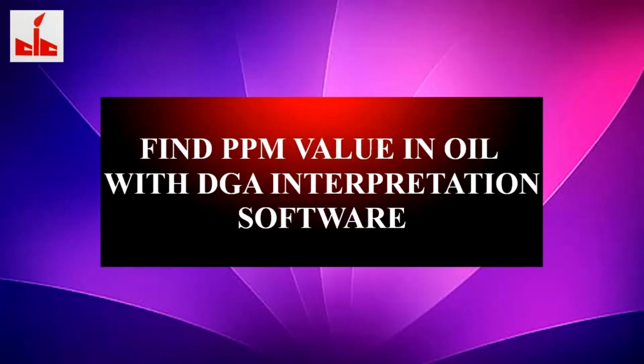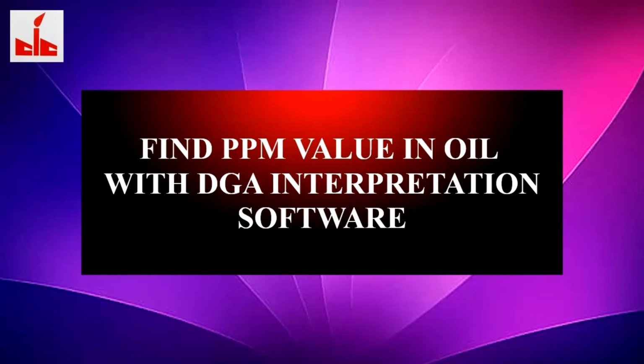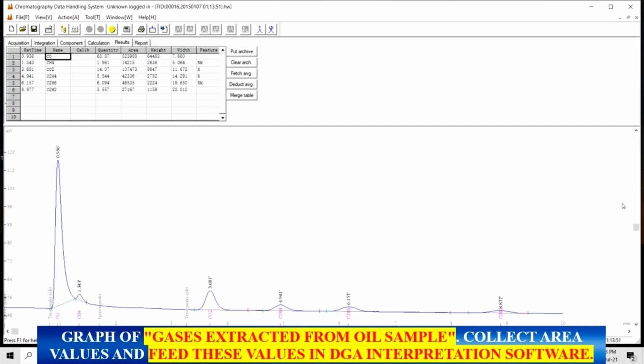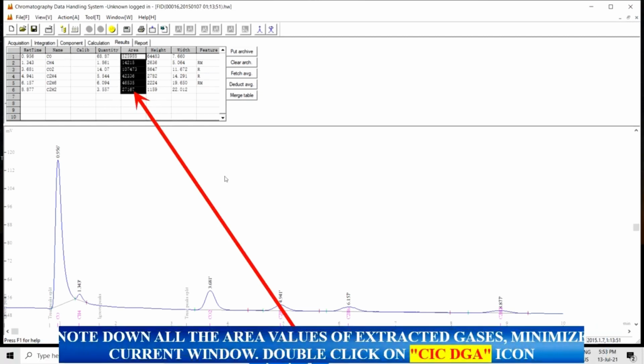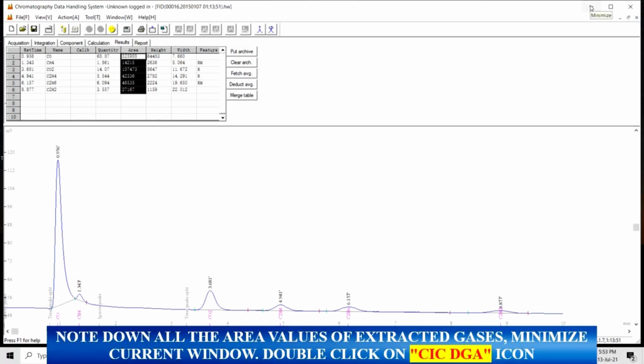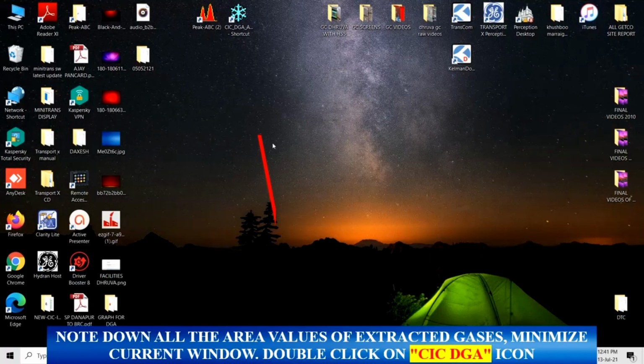Find ppm value in oil with DGA interpretation software. Graph of gases extracted from oil sample. Collect area values, and feed these values in DGA interpretation software. Note down all the area values of extracted gases. Minimize the current window. Double-click on the CIC DGA icon.